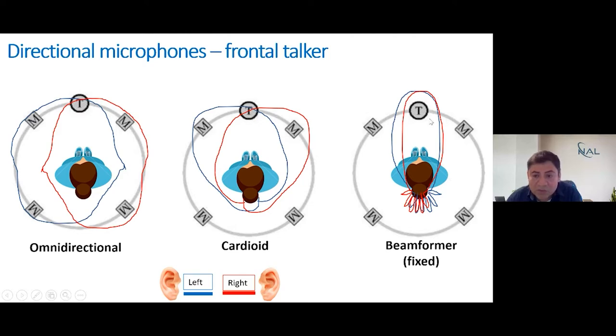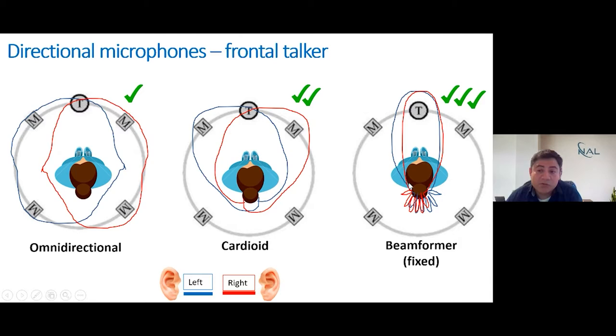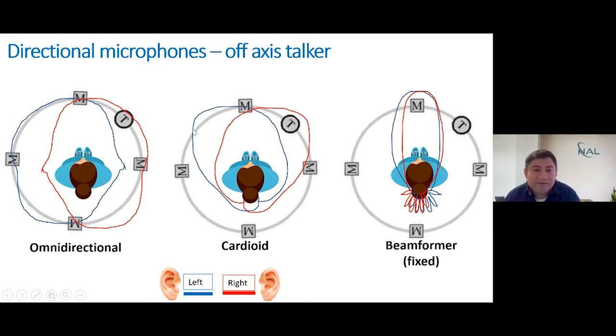Research shows that these arrangements help you understand target speech in noise configurations. Cardioid does slightly better than omnidirectional, and beamformers give a significant improvement in speech understanding in noise because the beamformer focuses more specifically on the target while attenuating pretty much everything else, so the listener has less trouble hearing speech from the target location.